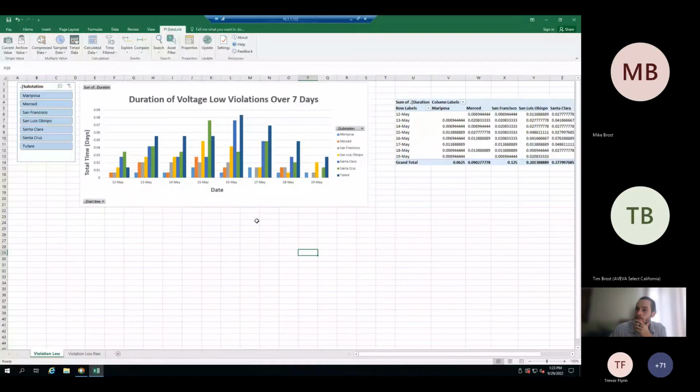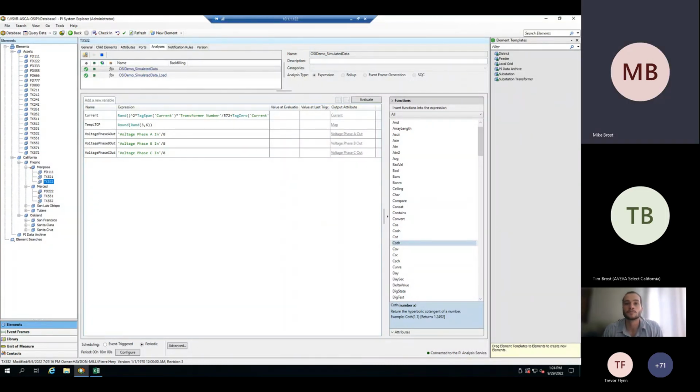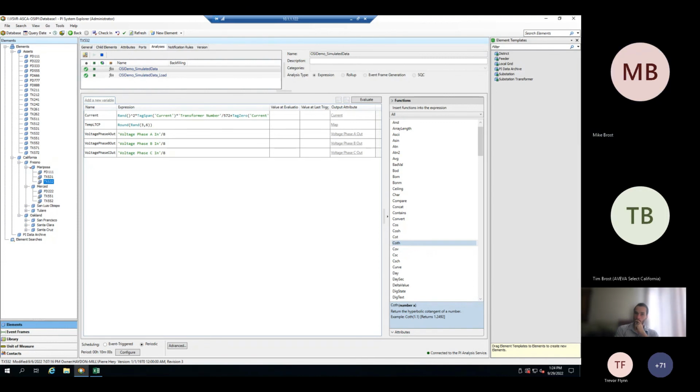We were using the Wonderware connector from the AVEVA historian connector to PI, and that's been problematic. I think actually Mike has helped me out in the past getting that fixed when it's broken. Which connector are you talking about? Sorry. Yeah, so there was a connector made. In fact, we helped OSI create it, but it was very limited in what they could do with that connector because the APIs of replication weren't available publicly. And replication solves every problem that connector had. It really is the way to go in the future. Gotcha.